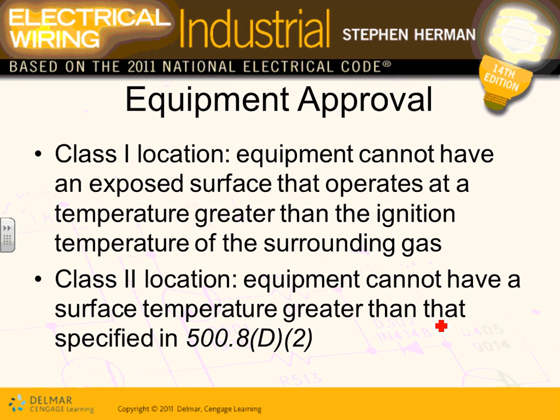Okay, classified locations. In a classified location, guys, the equipment that you install cannot have an exposed surface that operates at a greater temperature than that which will ignite the surrounding gas. So that's the most important thing. When you put in a fixture like this, the external temperature of that fixture cannot exceed the igniting temperature of the gas. Otherwise, you're going to have an explosion. That's the key when it comes to putting equipment in a hazardous location. In a Class 1 location, with gases and vapors, you cannot put a switch or a circuit breaker or a fuse that will create heat on the surroundings that will reach the igniting temperature of that gas and cause an explosion.